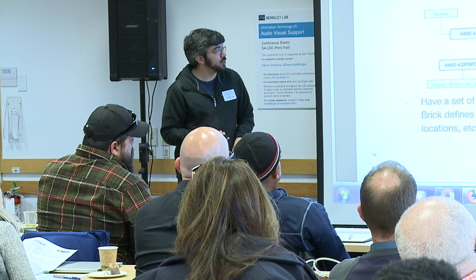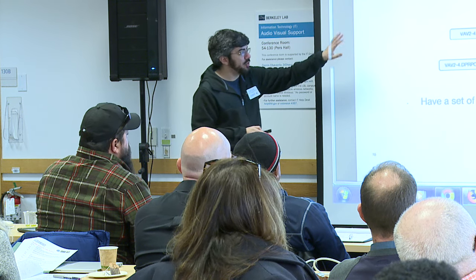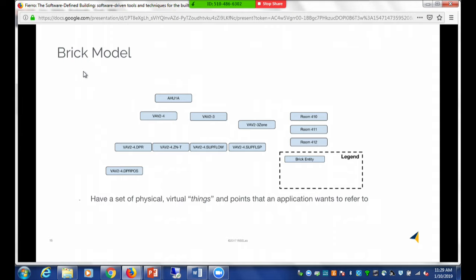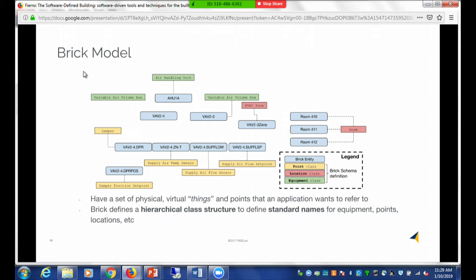So as an example, I've named all this set of things — these are your classic names. DPR POS was, of course, a damper position. SUP FLSP is, I think, a supply airflow set point. So we can put actual labels on these — I don't have to decipher that anymore. Say, that's a damper position set point, that's a supply air temperature sensor.